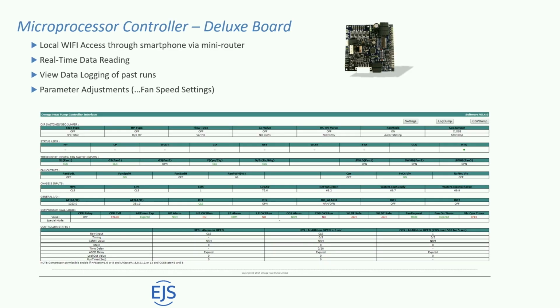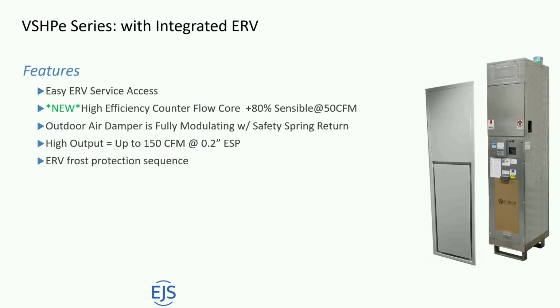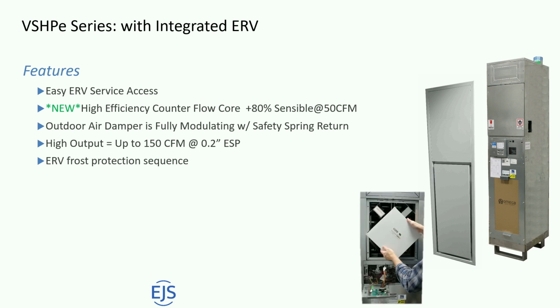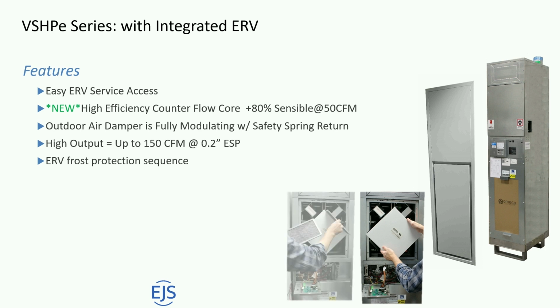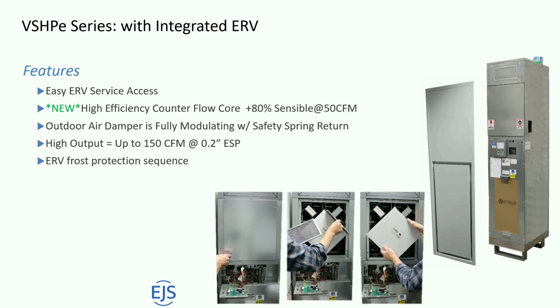Through the controller, we can see a lot of the temperatures, refrigerant temperatures, water temperatures, air temperatures, especially in a geothermal loop when we're talking about thermal balancing. Knowing what those temperatures are at the water side is very important. Techs can actually dial in and see what those water temperatures are. Here's your ERV, which we touched on earlier. We can get 80% sensible efficiencies, which do meet the passive house requirements for heat exchange from the outside air through the toilet exhaust. These are pictures of access.